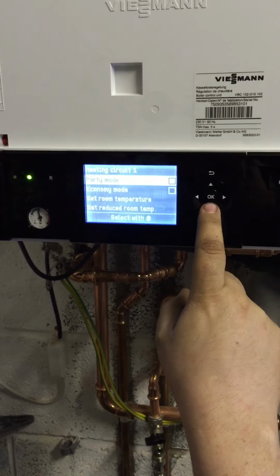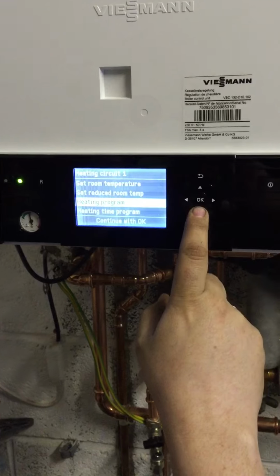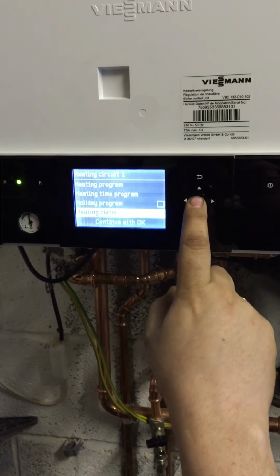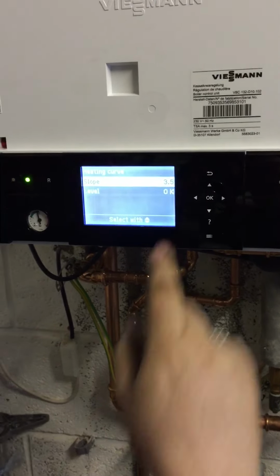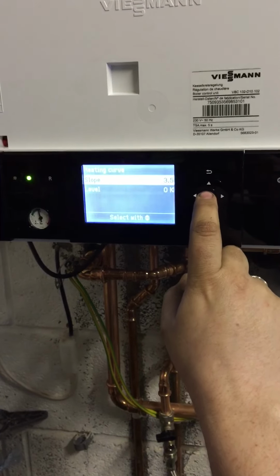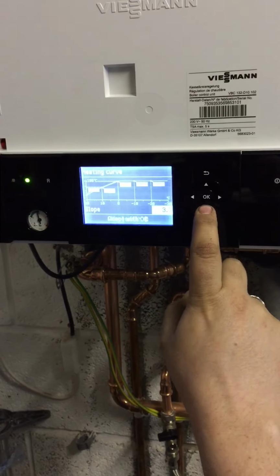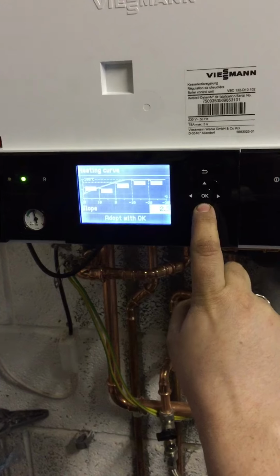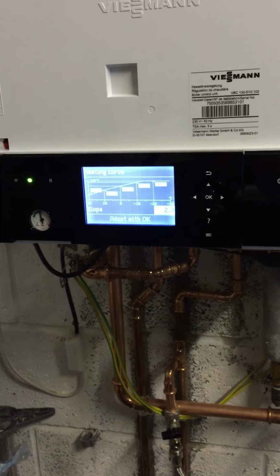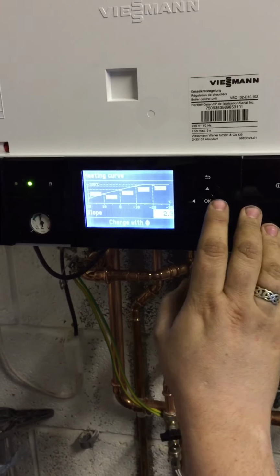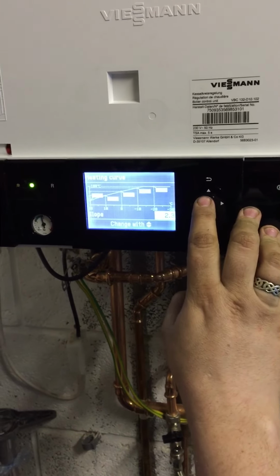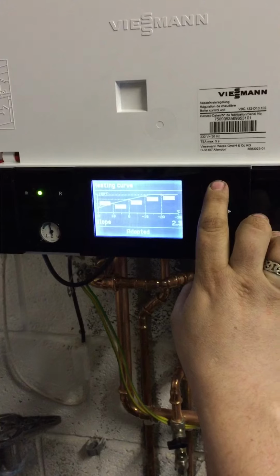onto heating there, and we go down to the weather compensated heating curve, the slope at the moment is at 3.5, which is far too high. We're going to cook the customers with that. We'll drop that down. I'm going to drop it down to about 2.3 for this property. It's still a very high curve, and I'll explain to the customer that after a couple of days to start dropping that down to try and find the best happy medium for that. So we've just adopted that there.